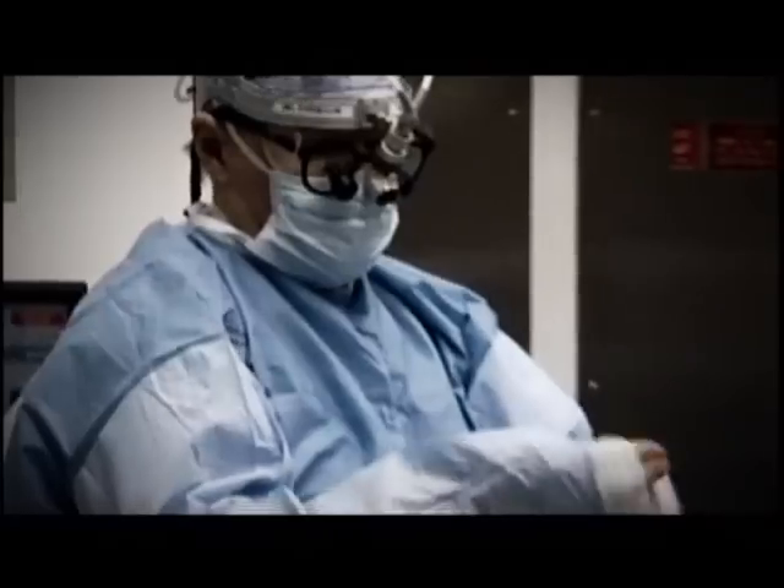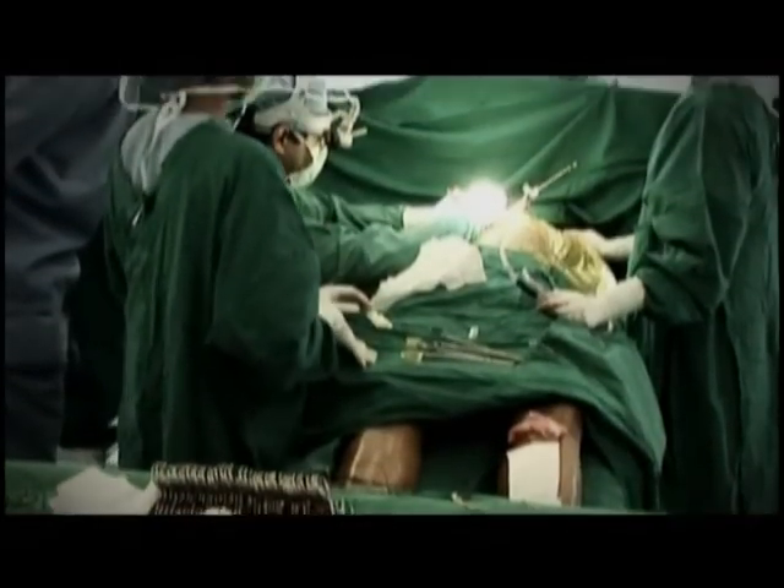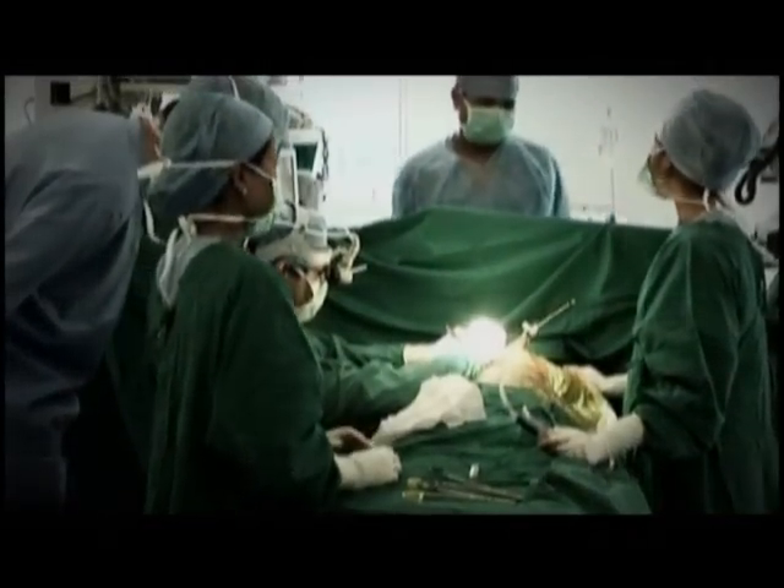Other attempts to help doctors and nurses have centered on 3D imaging that requires headsets and complex software. The breakthrough was that if you just use a mirror and a display and mount it on the transducer, then it's a 2D image. You look through the mirror and you see it where it actually is, and therefore a nurse and a doctor can see the same image, and they don't have to both be wearing helmets.